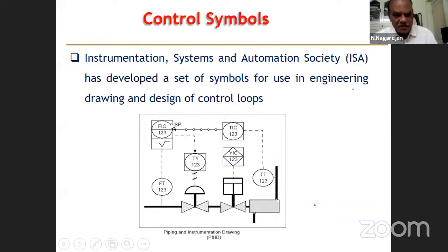It goes to your control block. This is called flow indicating controller, FIC 123. This is the DCS symbol. A circle inside a square is the DCS symbol. Then the set point comes here. There is a temperature measurement, and we are linking two variables here. Temperature measurement TT123, and then TIC is the temperature indicating controller, and then the temperature set point goes here.